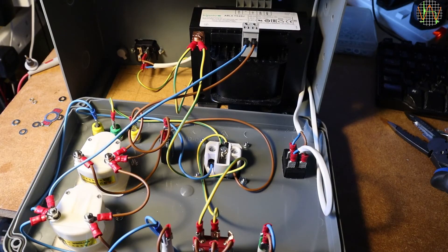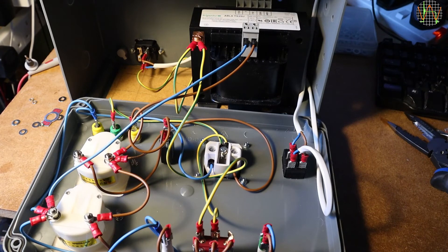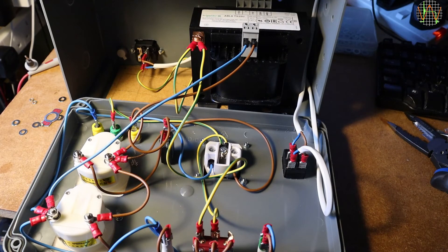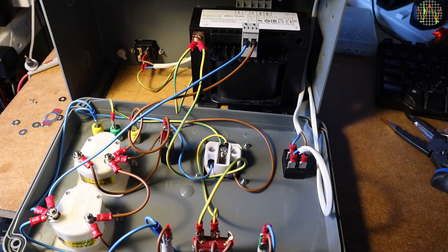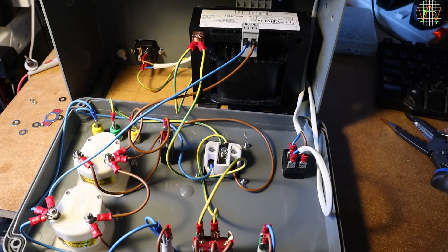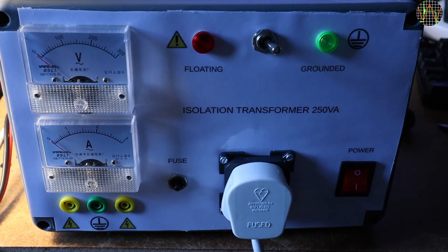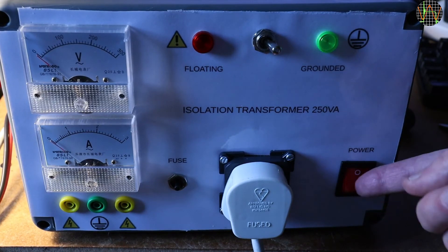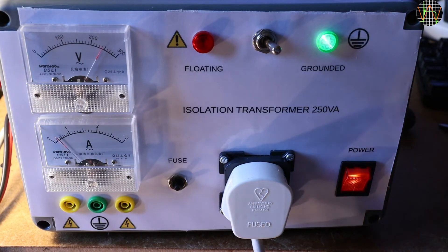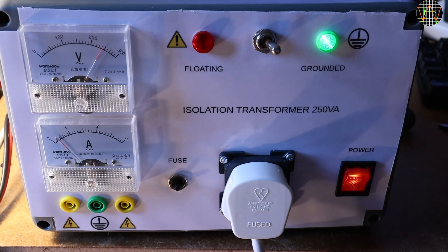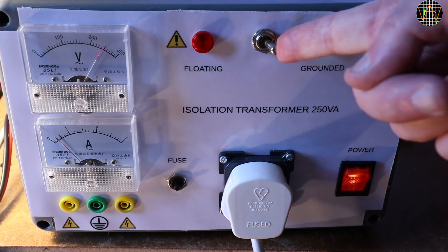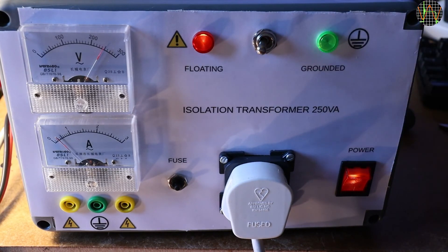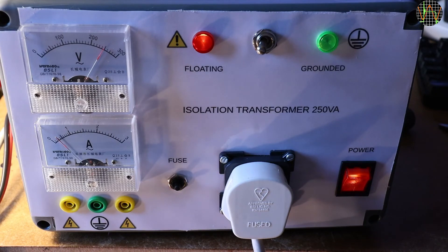This is the fully wired up unit. The three cables you just saw are connected to the secondary of the transformer and earth while the previously prepared cables for the primary are plugged into the rear of the power switch. Testing the isolation transformer is not very exciting. I have two 60W incandescent light bulbs plugged into the output to see at least some movement on the ammeter. As you would expect, nothing changes when switching to floating, at least not when using simple light bulbs.